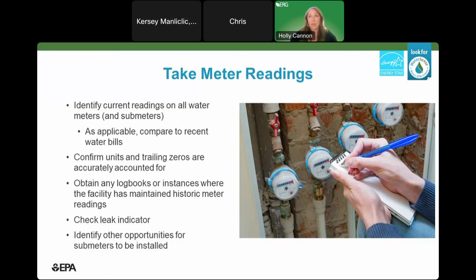If there's a cooling tower makeup water meter, you definitely want to take a look at that and read it. When you're looking at meters, check the leak indicator, usually a spinning black or red dial or another indicator on electronic meters. If you're not expecting water use at that time, that's something to look into and verify.